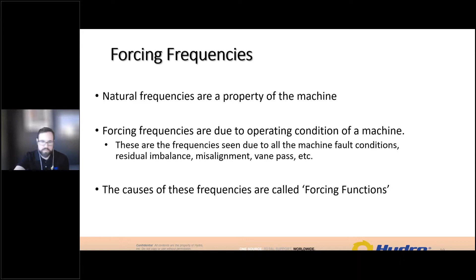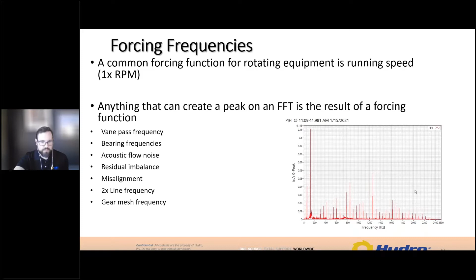The most common forcing frequency you'll see, probably what everybody knows, is vibration at the run speed of the machine, or 1 times. That's very often due to imbalance or some mechanical fault, and lots of different mechanical faults show up as 1 times vibrations. But there are lots of other peaks too: vane pass, bearing frequencies, noise due to acoustical effects or flow noise, line frequency, gear mesh frequencies, belt frequencies. All these different peaks that show up in your spectra are frequencies of interest when it comes to resonance.